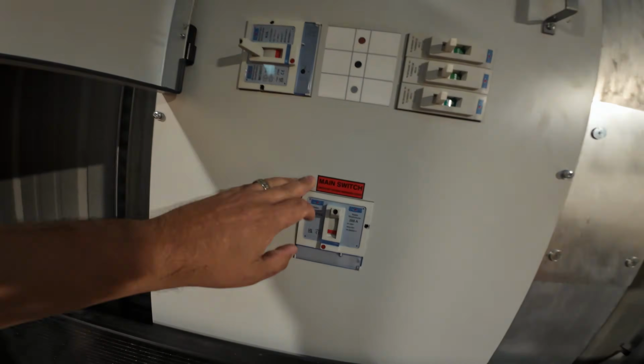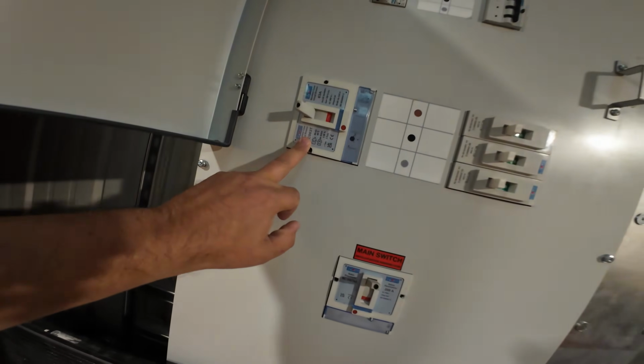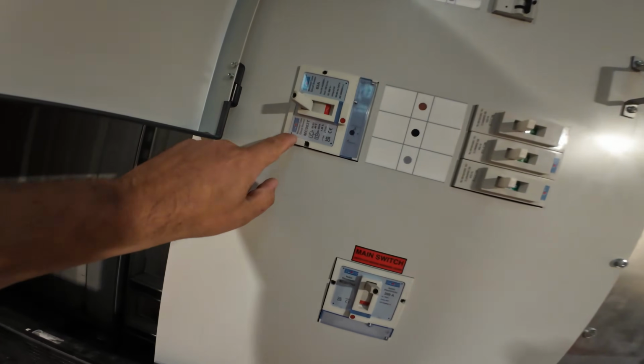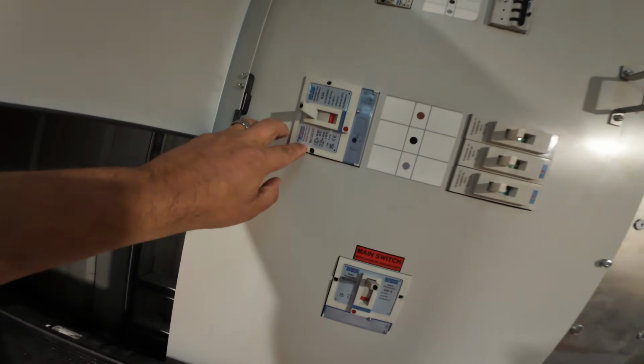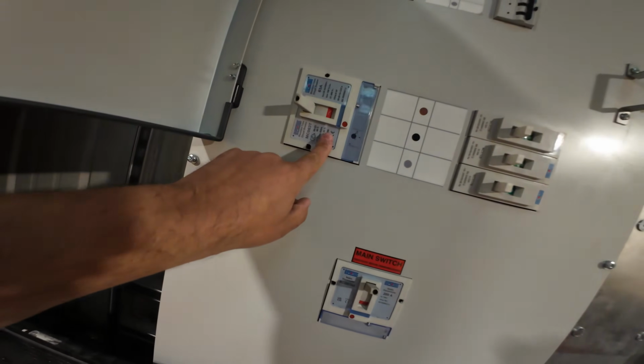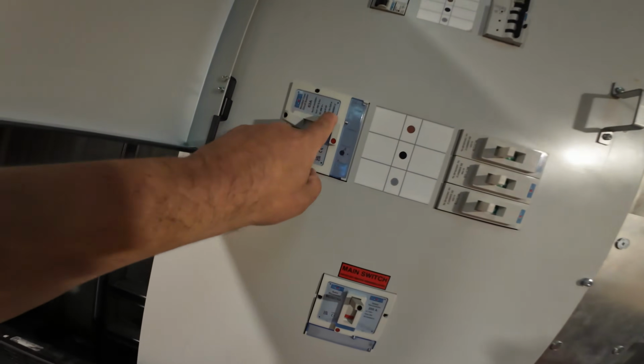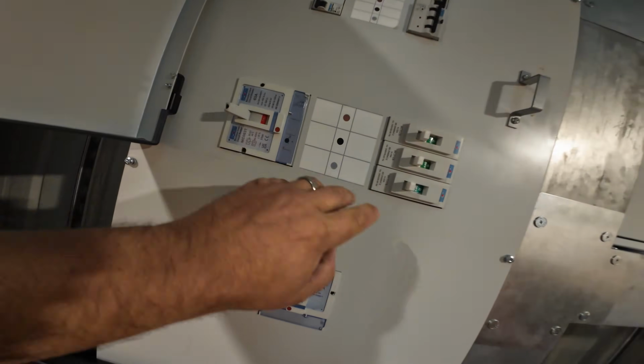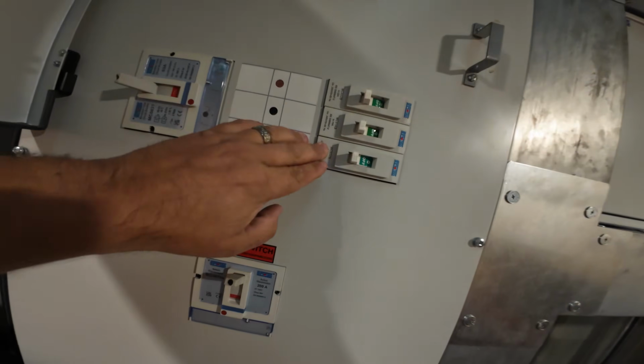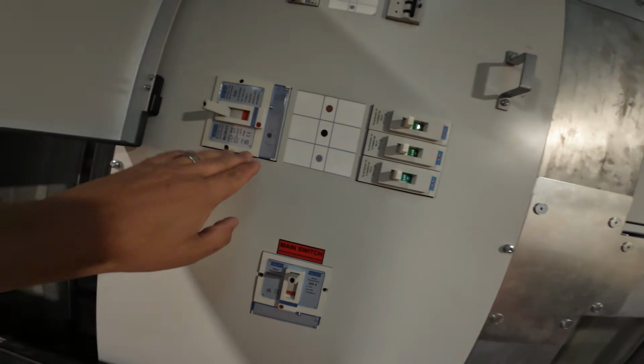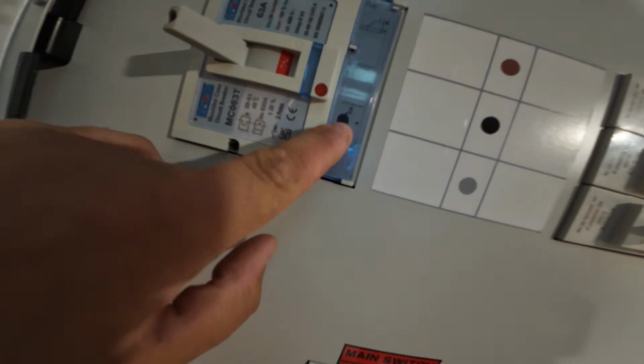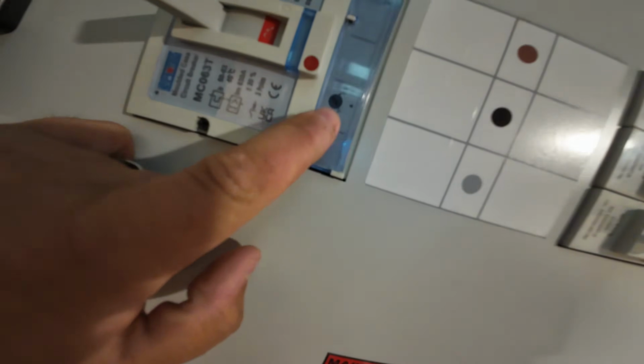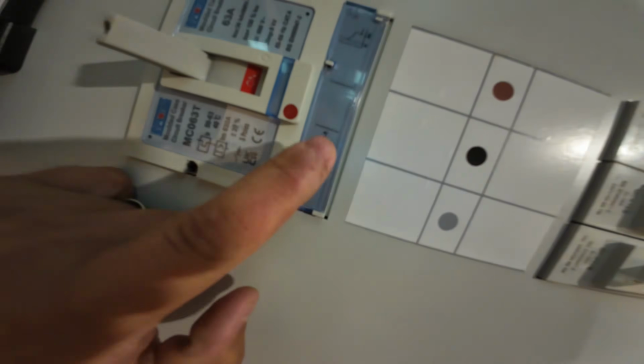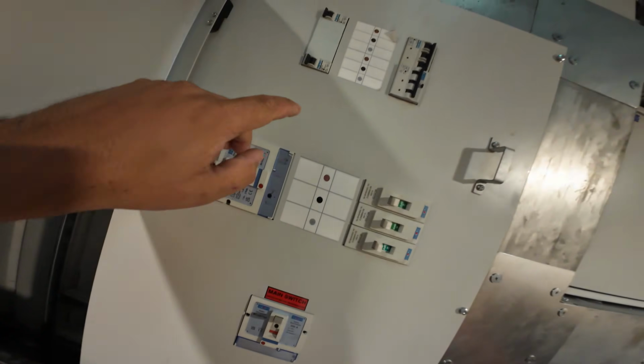So this is your switch disconnector. This is a large 3-phase MCCB, which is a moulded case circuit breaker, and this is a 3-pole variety, and you can see it's that product standard 60947-2. This is the same product standard, but these are just single phase options of that. And you can see one of the other things you get when you are going into the realms of 60947-2 is this adjustment in the tripping curves of them as well.